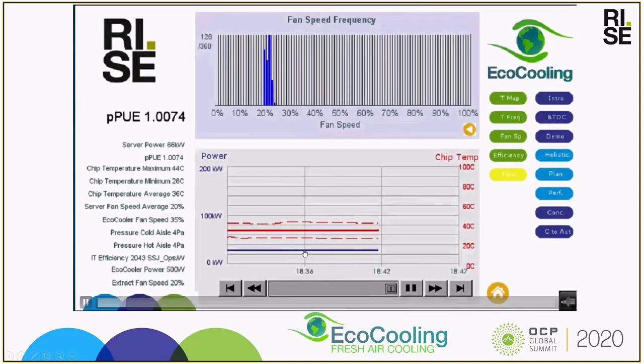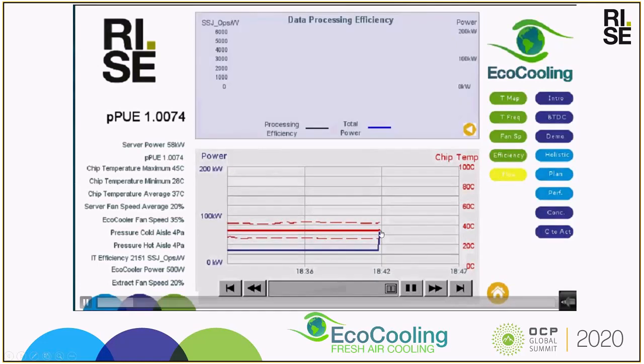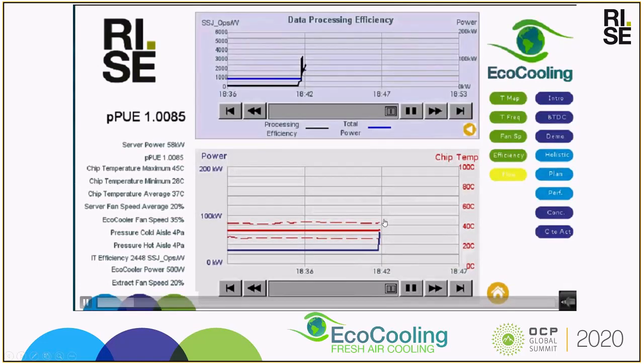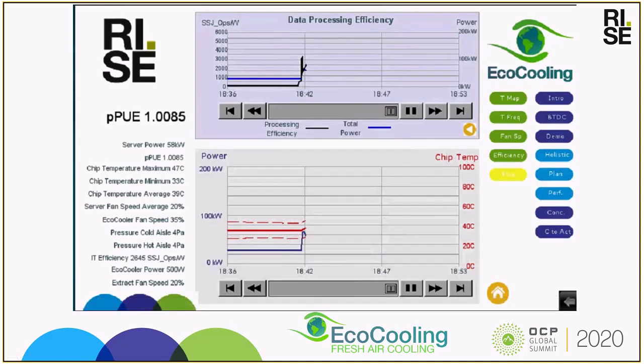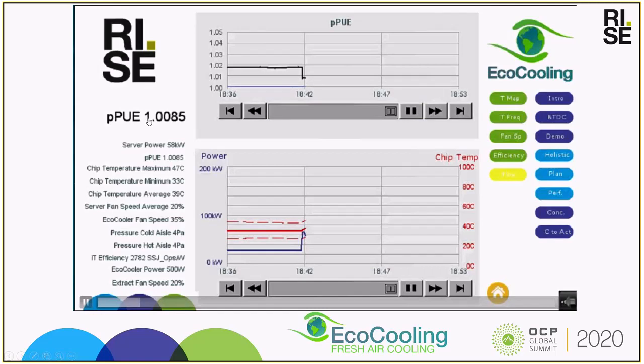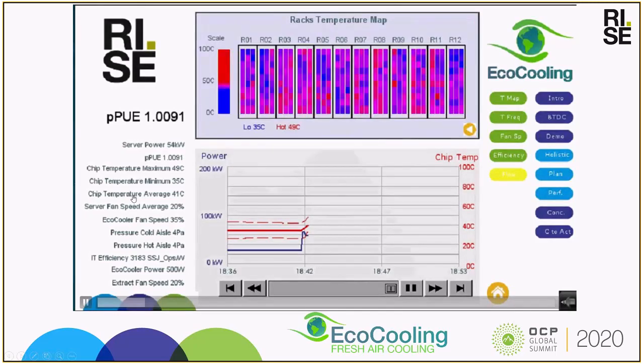The blue line here is the IT power draw, and now you can see it's going from the 28 kilowatts it was at just a moment ago, and it's now starting to increase to 58 kilowatts. On the left here, we are calculating the partial PUE, the instantaneous value, which is also graphed at the top here. We are monitoring the chip temperature, the average chip temperature, and the minimum and maximum, which produces the heat map here.